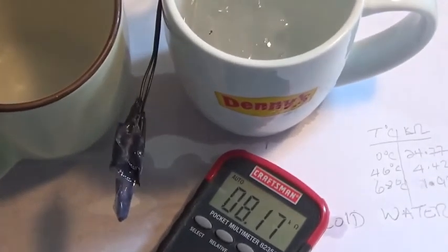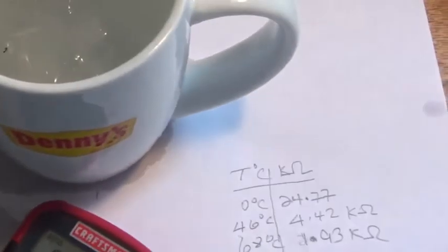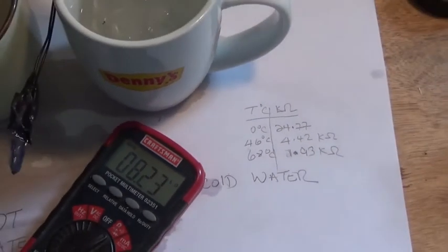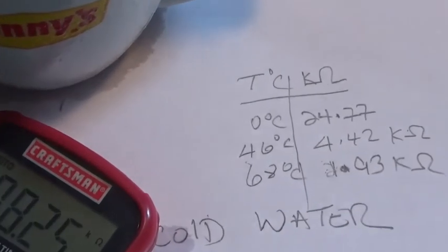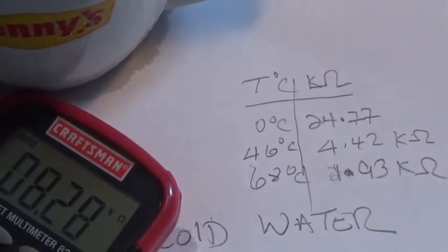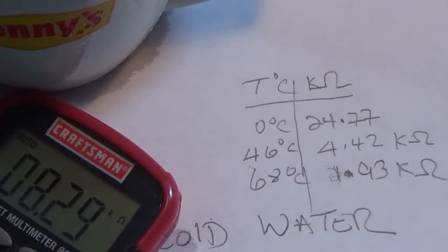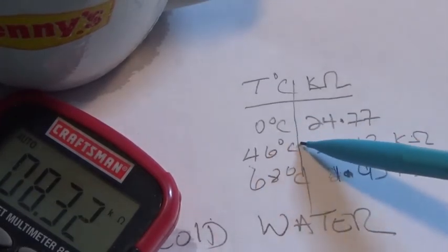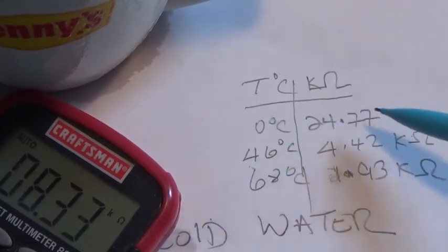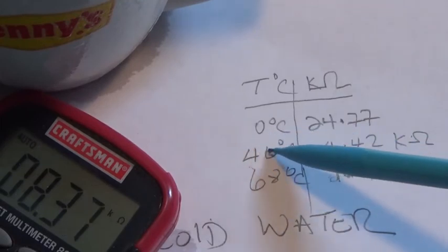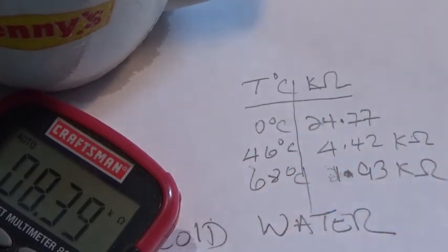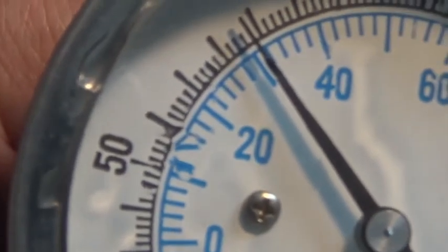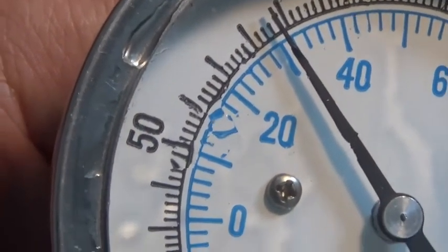Let's make this so you take a deep look at what I'm doing on my calibration curve. That point will be somewhere obviously between 0 and 46. It will be somewhere here, because I'm reading a resistance value of 8.33. So the temperature will be between these two, which roughly, let's see what I got here on my sensor. See if you can read it right here with me. It's about 32. I'm dropping. It's going to get to about 30 somehow.